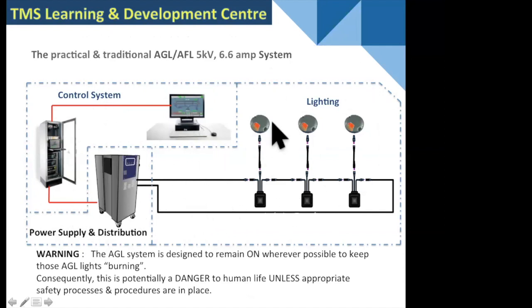But here we're going to talk about this area. Bear in mind a traditional system, 5 kV, 6.6 amp system, which is used pretty exclusively around the world. The voltages on the output terminals of this machine, for a 30 kVA CCR, could be up to 4,545 volts across there. All this equipment is rated for 5,000 volt operating. 5,000 volts kills and 6.6 amps kills.